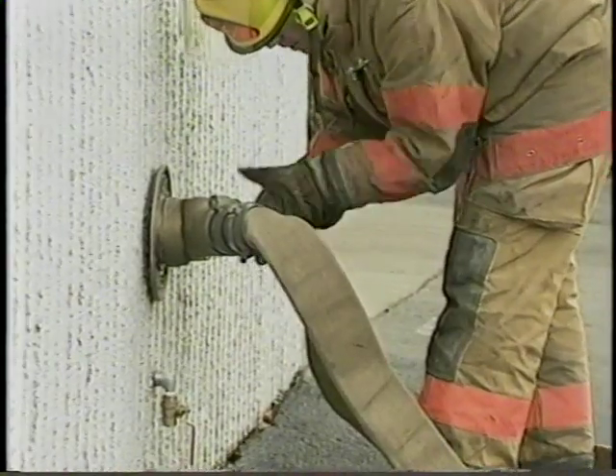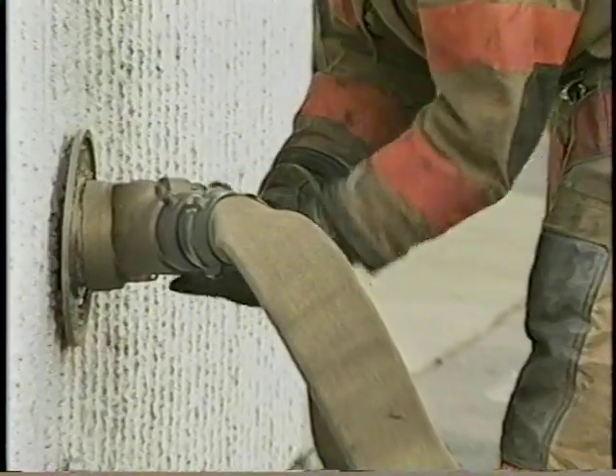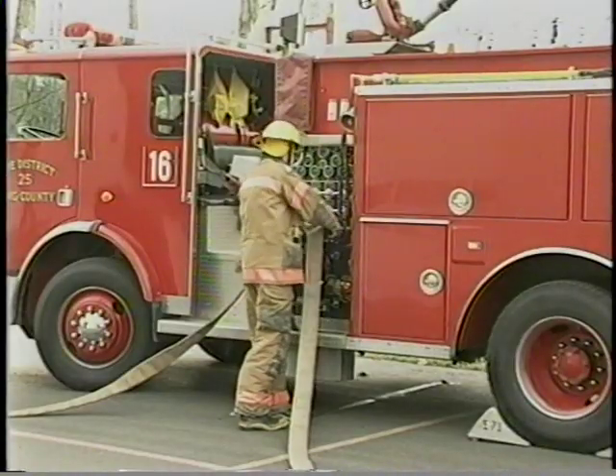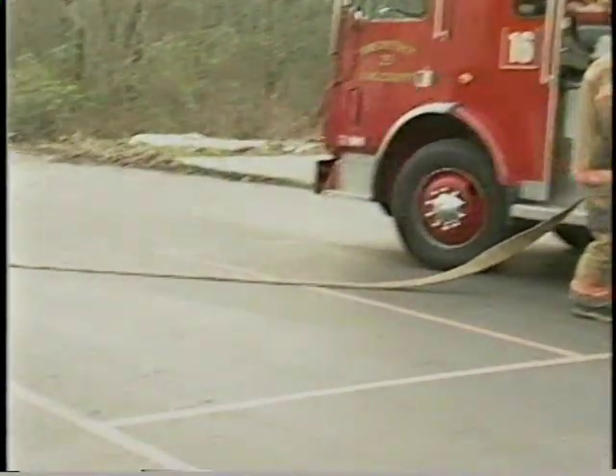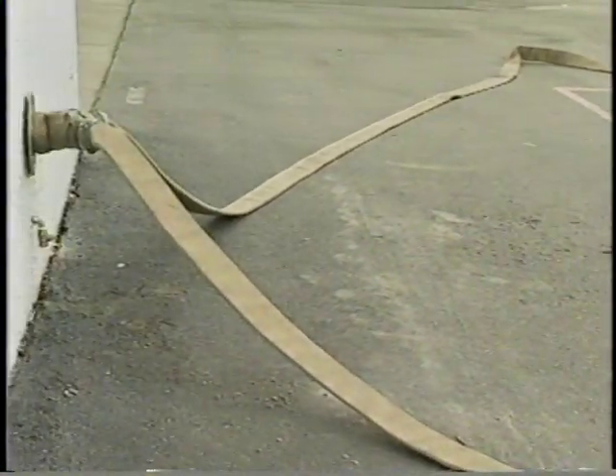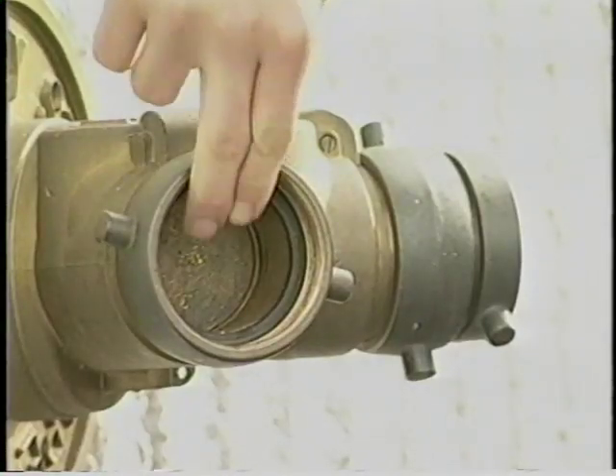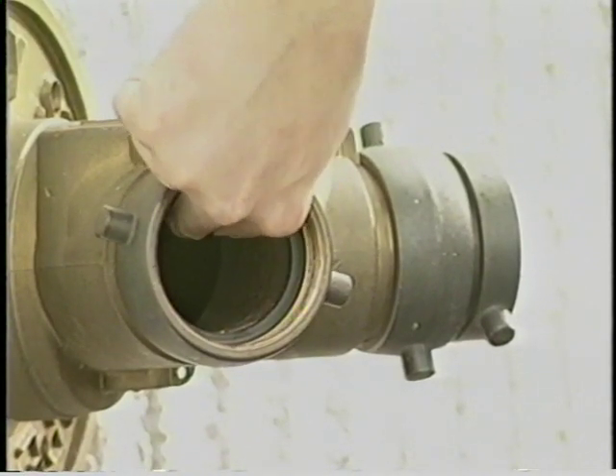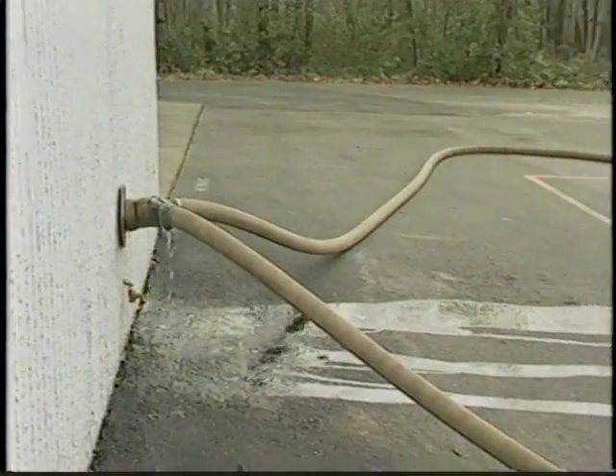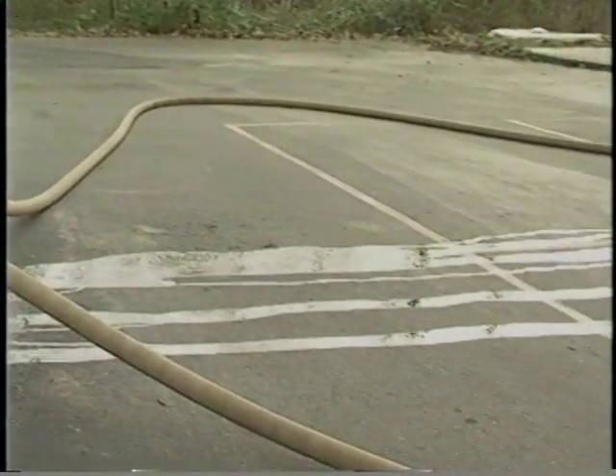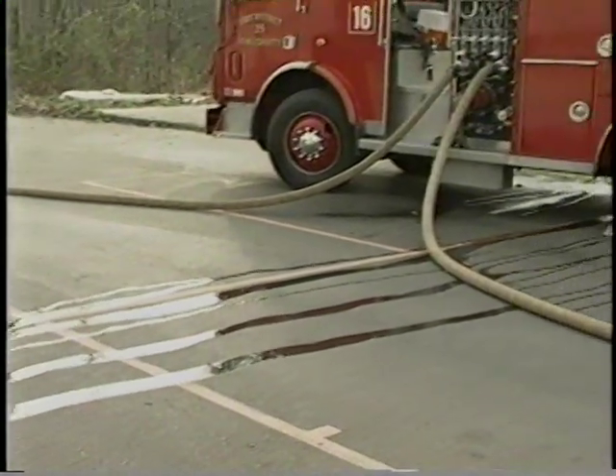Additional water and pressure can be provided by a pumper that is connected to the fire department sprinkler connection. As water flows into the system from the fire department connection, it first passes through a check valve. This valve prevents water from the sprinkler system from flowing back into the fire department connection.